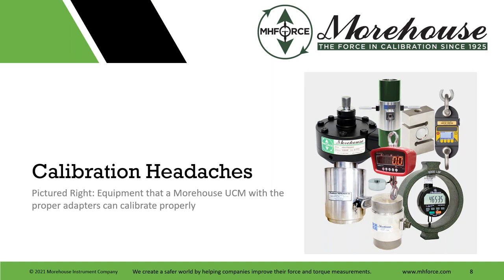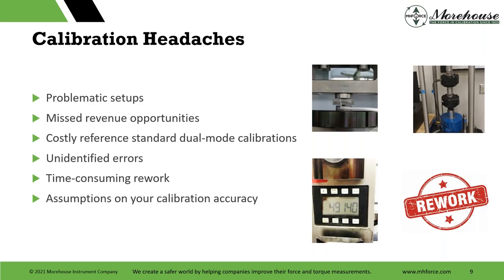In any case, the UCMs are called universal because they can calibrate almost anything with the proper adapters, and they're just thrown a hodgepodge of different equipment, from button load cells, tension links, dynamometers, S-beam load cells, force gauges, you name it. Some people have even gotten cable tensiometers in the machines. I don't really recommend that. We have our own machine to do cable tensiometers. That's much safer than putting them in a UCM, but they've done it.